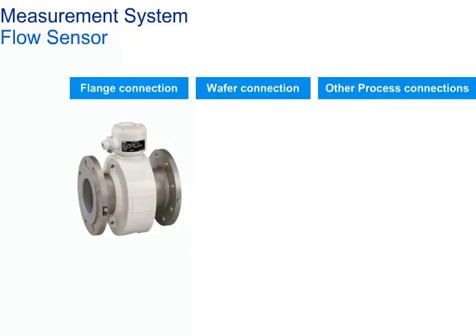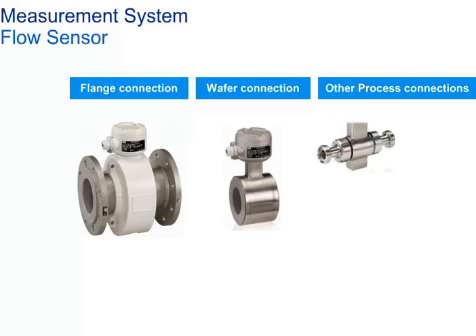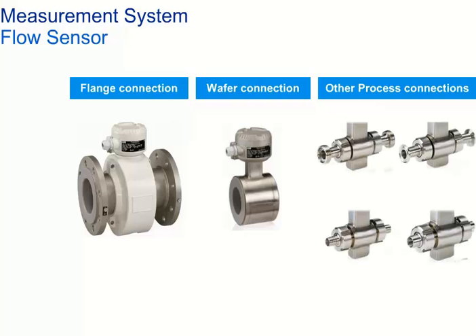Three different types of process connections can be found in the market. Flange type connection is the standard across major industries, available from DN10 to DN2400. Wafer type connection is a cost-effective alternative, available from DN10 to DN100. For hygienic applications, specific requirements such as cleanability or a gap-free transition from pipe to meter tube without crevices must be met — weld stubs, food industry fittings, male threads, or tri-clamps are used here.